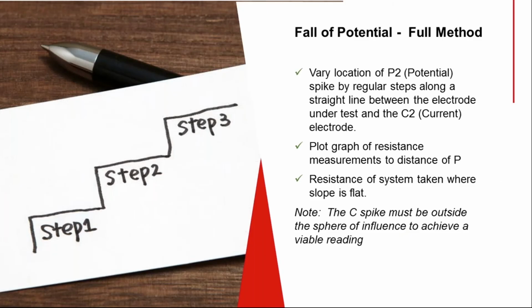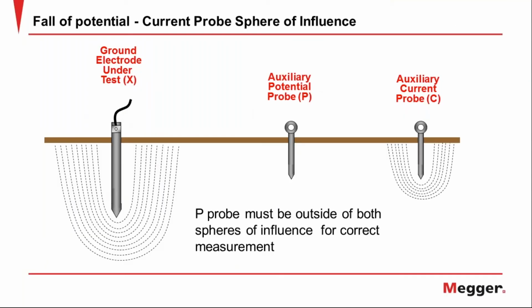Okay, this just kind of summarizes a little bit what we're doing here, and you're going to plot a graph. That's key to the success of this function. So note here, this is your layout. The broken lines there indicate an electrical field. The electrical field, theoretically, goes forever, but in a practical sense, fortunately, it does not go forever. The electrical field is a finite area of soil around your ground rod. It can be relatively large if you're in bad soil, and relatively small if you're in good soil. But bear in mind that your current probe also has an electrical field around it as well. And we'll see what the significance of that is in a moment.